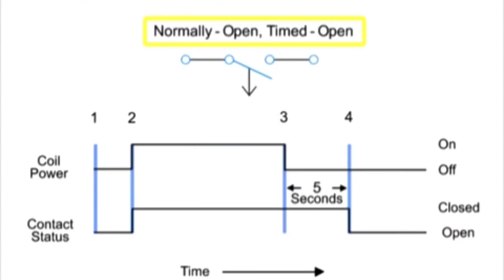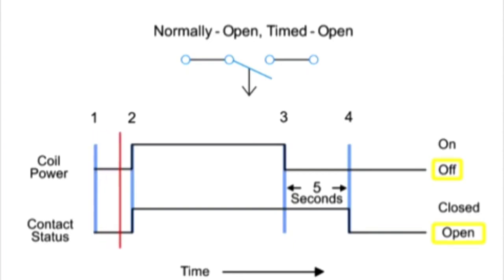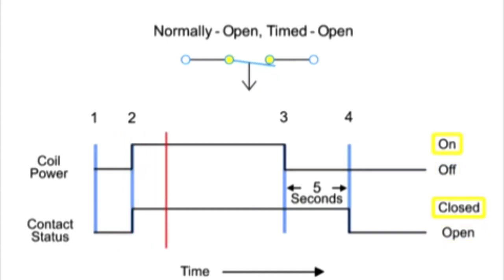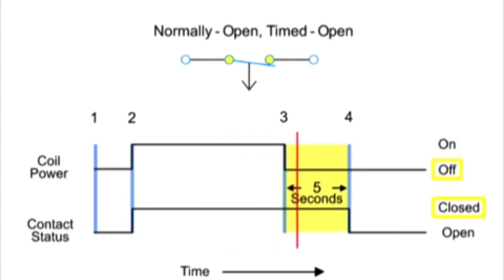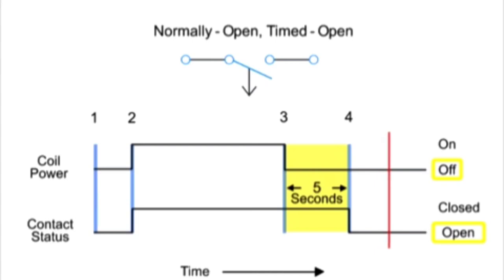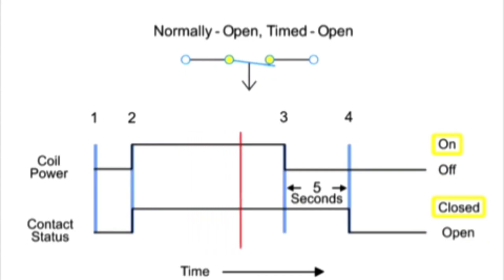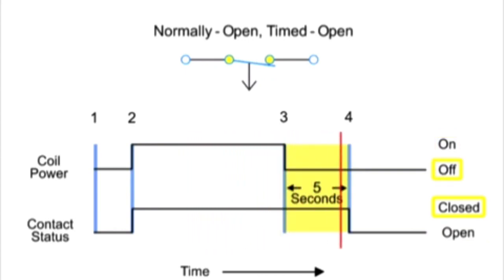Next, we have the normally open, timed open contact. Similar to the NOTC contact, this type of contact is normally open when the coil is unpowered or de-energized, and closed by the application of power to the relay coil. However, unlike the NOTC contact, the timing action occurs after the coil is de-energized for five seconds.